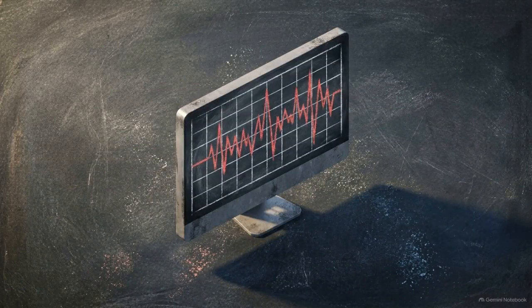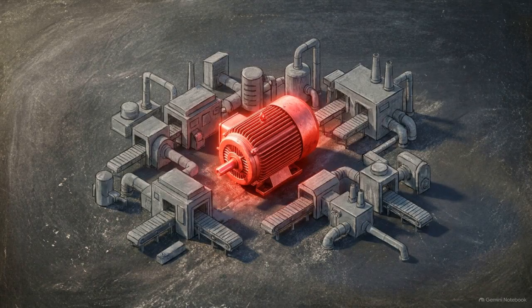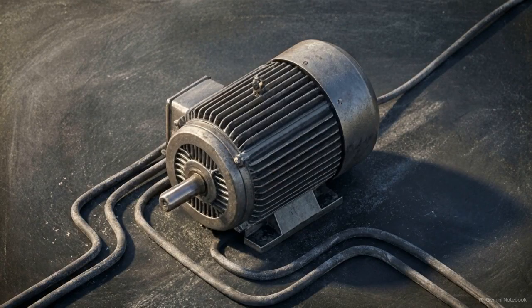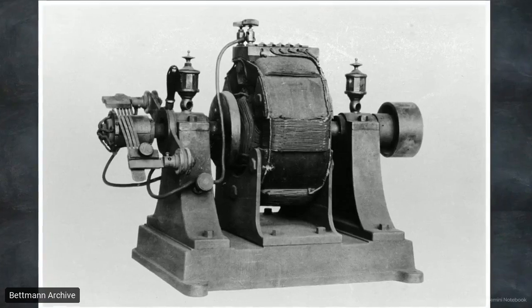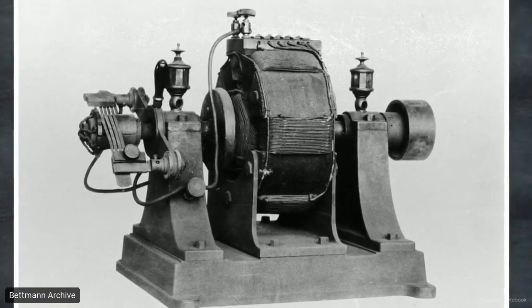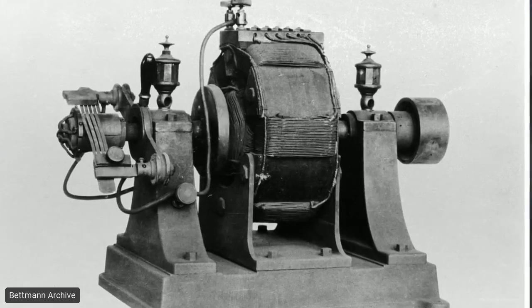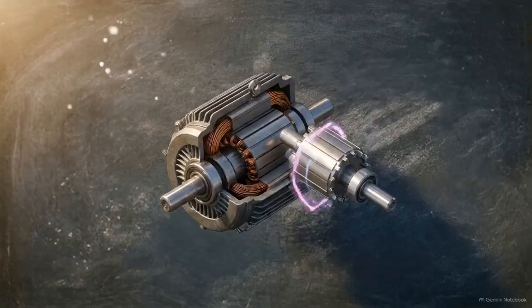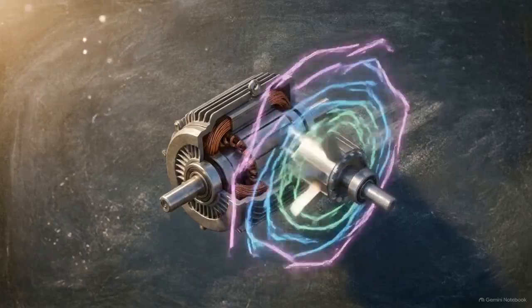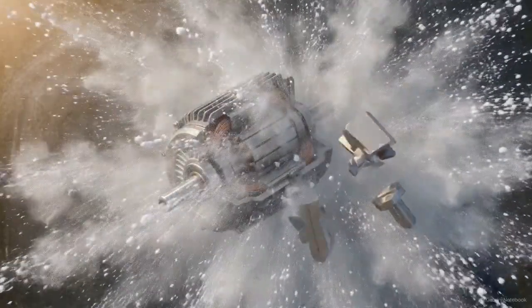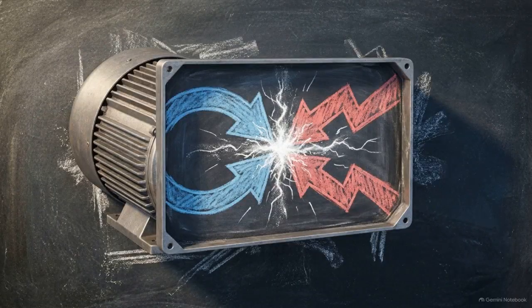By mapping harmonics directly to their sequences, engineers can look at a distorted wave capture and mathematically isolate the exact piece of nonlinear equipment causing the systemic unbalance. We can apply this identical theory down to the endpoints of the grid, heavy industrial electrical machines, like 3-phase induction motors. A healthy induction motor operates efficiently, drawing almost exclusively on positive sequence currents to generate rotational torque, with negligible negative or zero sequence presence. Snap a rotor bar or short a stator winding, and that perfect magnetic symmetry breaks immediately. The motor begins pulling negative sequence currents, which generate a counter-rotating magnetic field that fights the motor's own rotation.